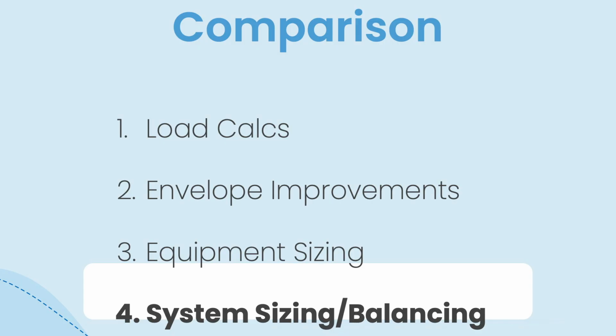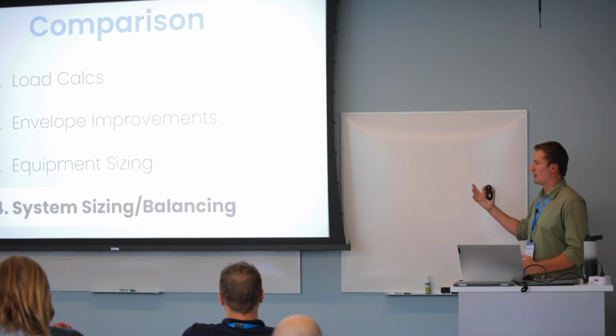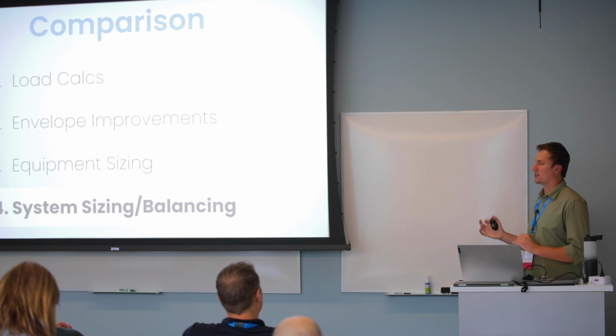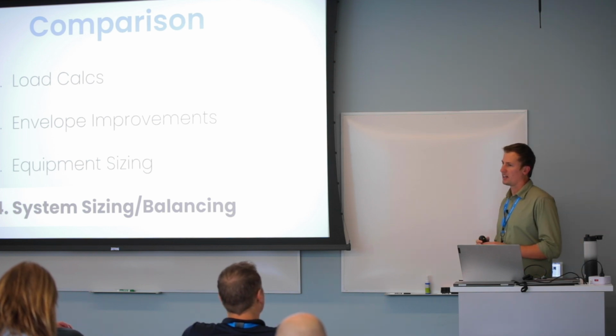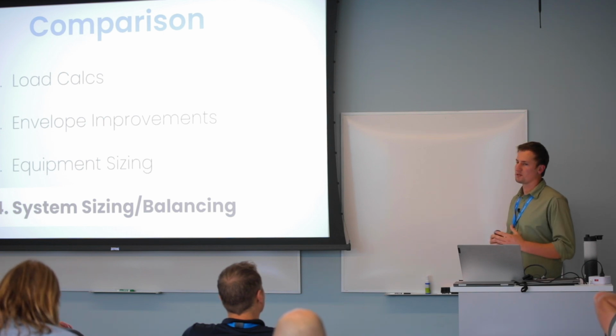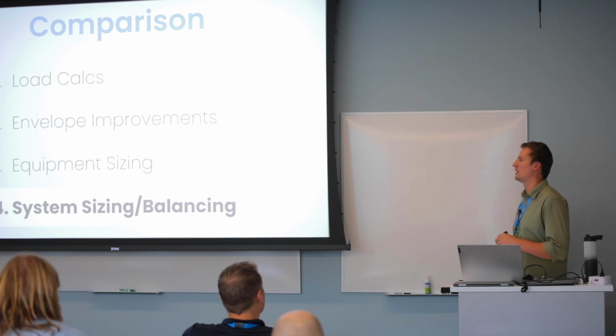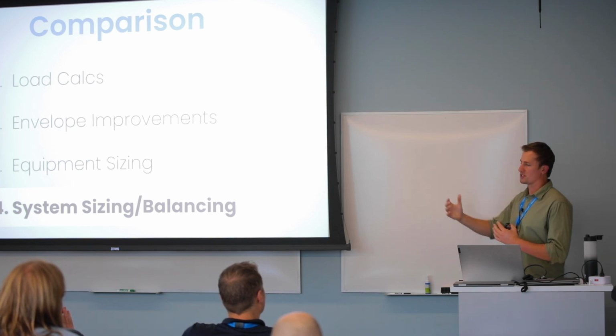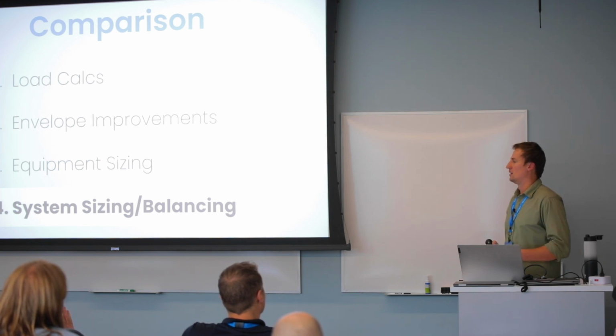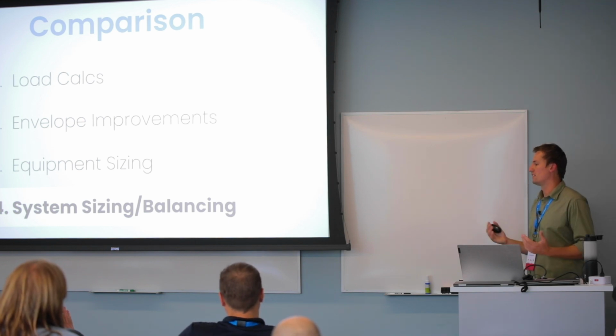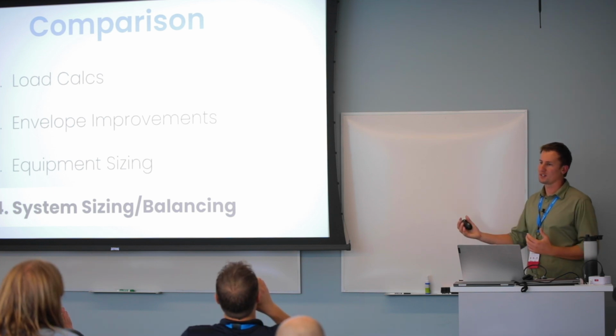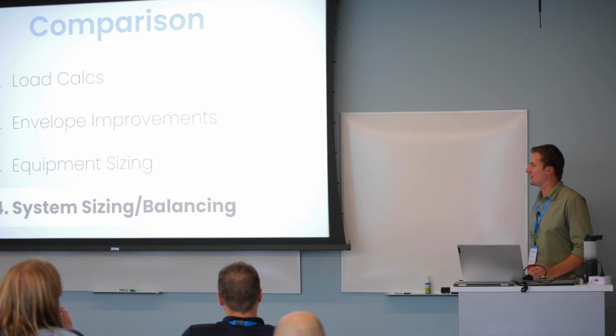All right, so if we move on to the last part of this, it is now sizing and balancing the system properly. Even if you've done all the three steps before correctly, which is more design, if you get to the site and you don't install it properly, and really I'm mainly talking about the balance inside. The air will try to take the path of least resistance. So the room furthest from the air handling unit is going to be quite hard to get to, whereas in the closest room, the air is going to want to go out there. So you need to make sure you balance your pressures. What you're trying to avoid is someone saying they're too hot and someone saying they're too cold, because that means the heat pumps are overworking once again.